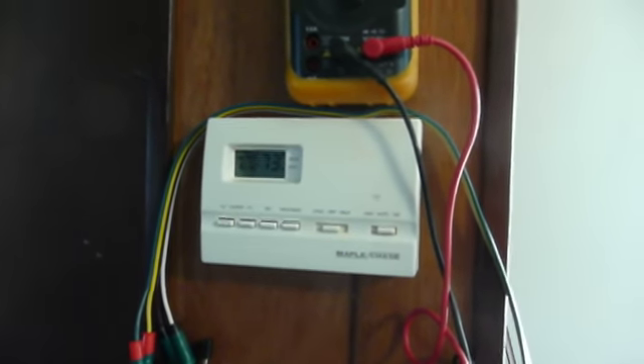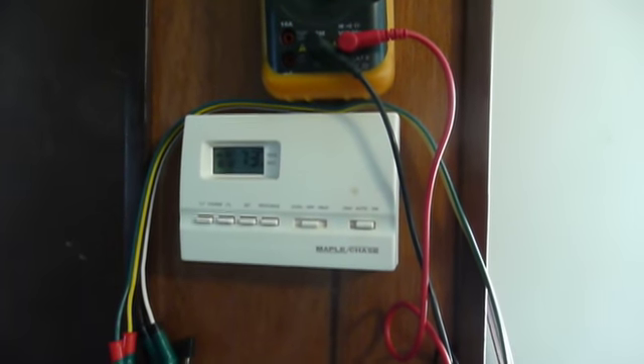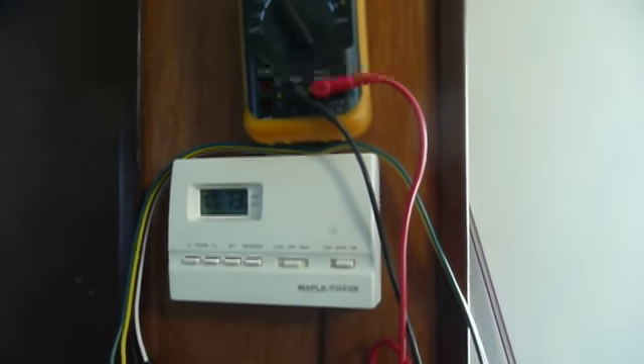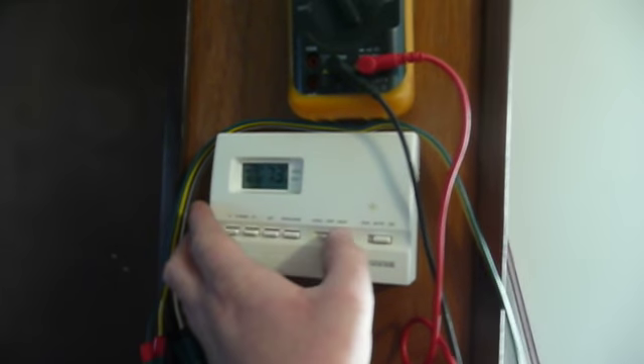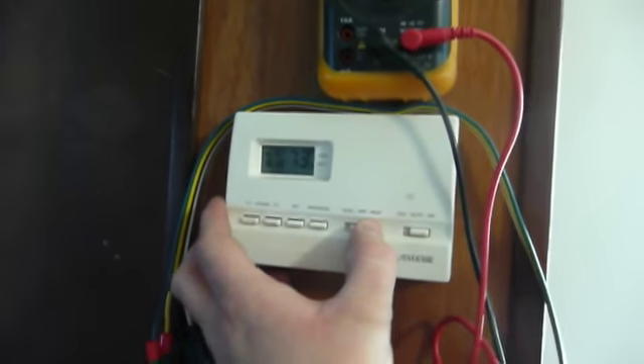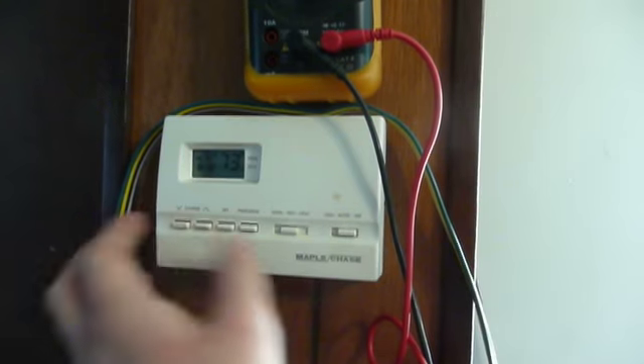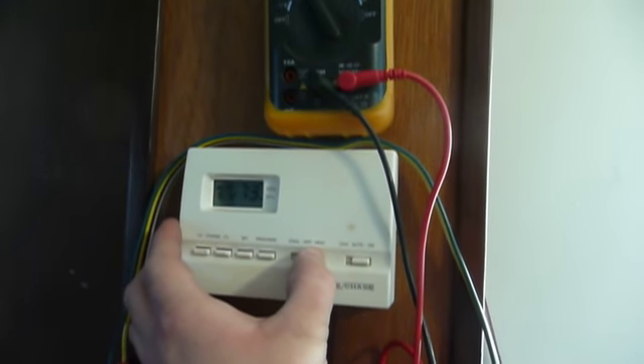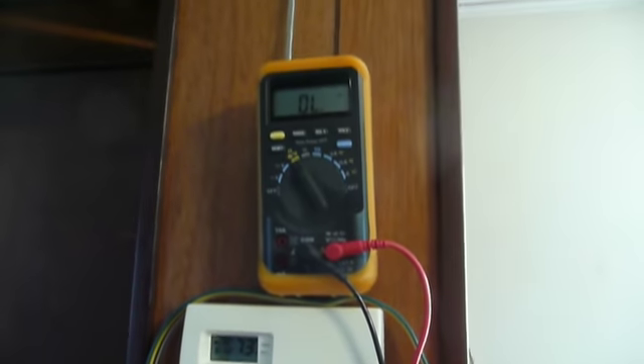Now the thermostat usually has a safety circuit in it to protect against repeated activation of the air conditioning compressor, because that would be very bad for it. So we'll check that too. This one has a 5-minute delay, and it hasn't been 5 minutes yet, so when I turn this on, the circuit should remain off. And indeed it does.